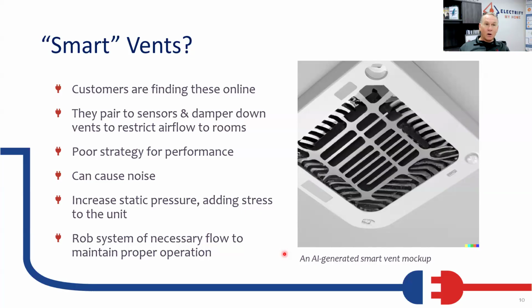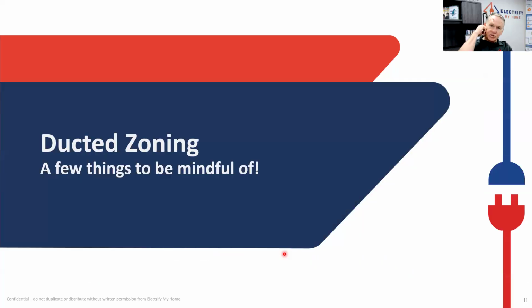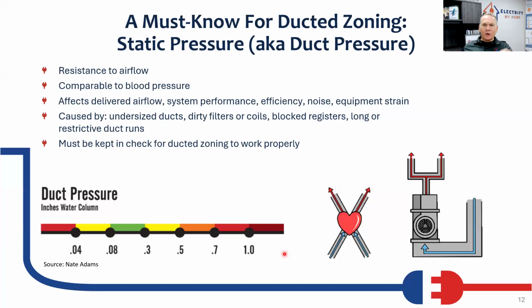So that means all those houses where we're dealing with designers are going to want those because they're beautiful, and they're going to cause problems with the system, no different than just stopping the air anywhere else in the system. Ducted zoning, if you're going to do ducted zoning, there's some things we need to be mindful of. We need to keep our static pressure in our systems at a reasonable number so that we can, one, not take out the motors.